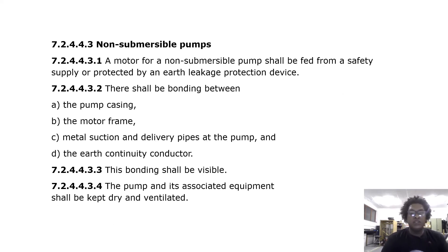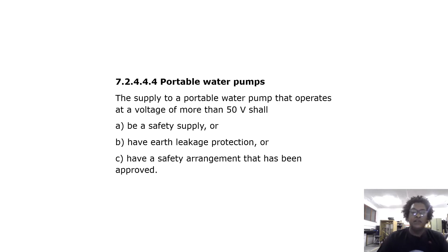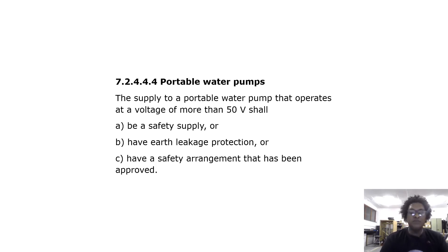A motor for a non-submersible pump shall be fed from a supply protected by an earth leakage protection device. There shall be bonding between the pump casing, the motor frame, metal suction and delivery pipes at the pump, and the earth continuity conductor; this bonding shall be visible. The pump and its associated equipment shall be kept dry and ventilated. The supply to a portable water pump operating at a voltage of more than 50 volts shall be a safety supply, or have earth leakage protection, or have a safety arrangement that has been approved.